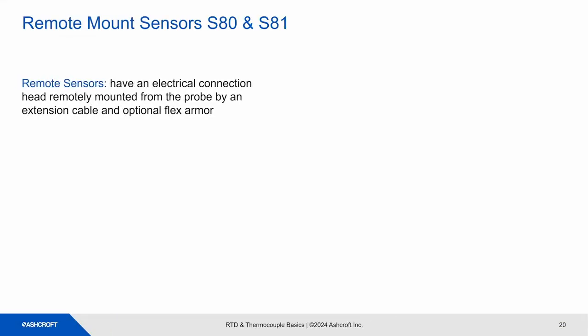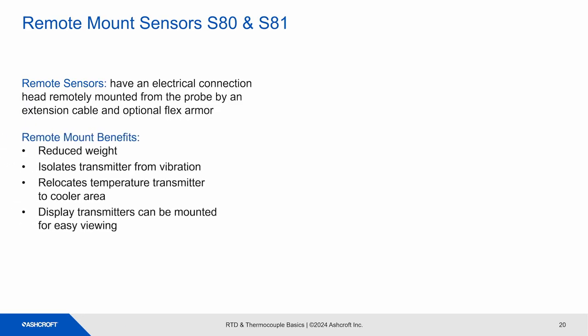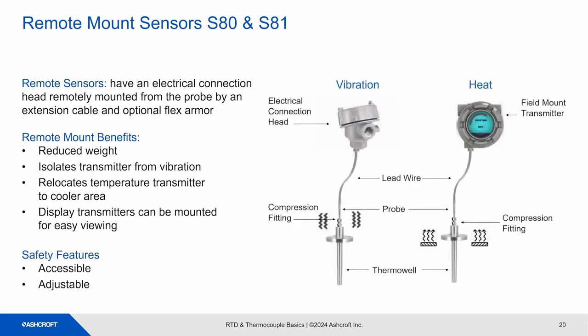S80 and S81 remote mount sensors. Remote mount sensors have their electrical connection head remotely mounted from the probe by an extension cable. The extension cable can be protected by encasing it in flex armor. Remote mount benefits are reduced weight. They isolate the electrical connection head from vibration and heat. Display transmitters can be mounted for easy viewing. Remote mounts are more accessible, and it's easy to adjust the head location and mounting.